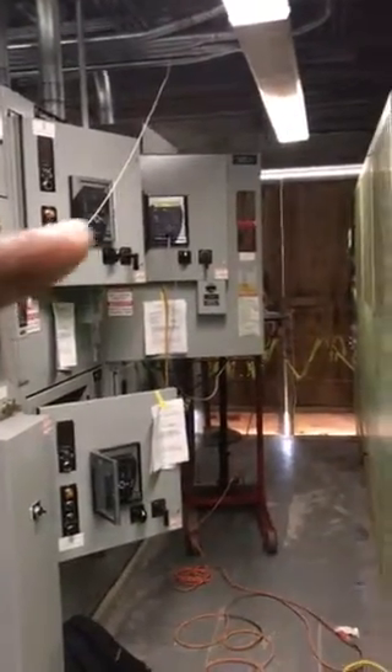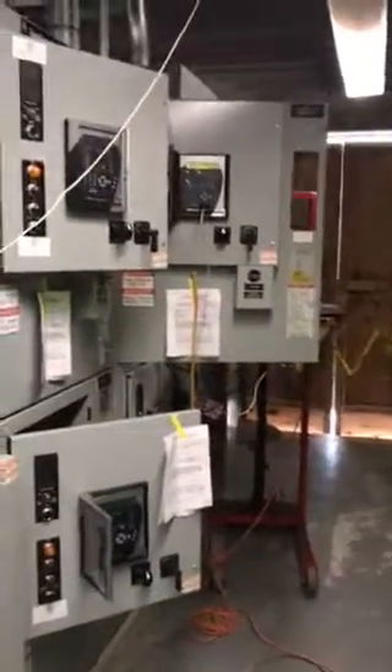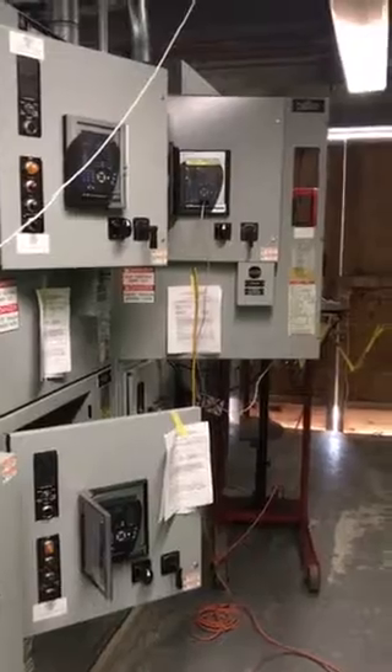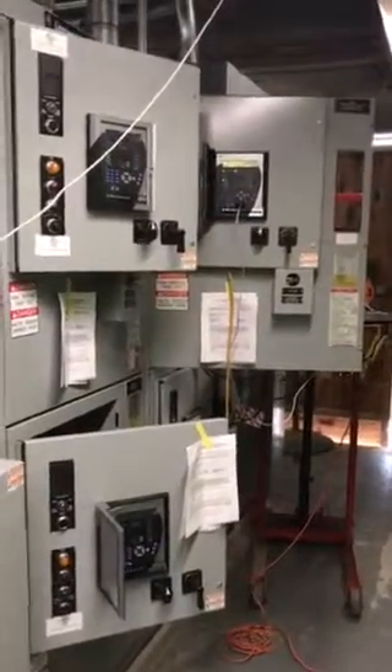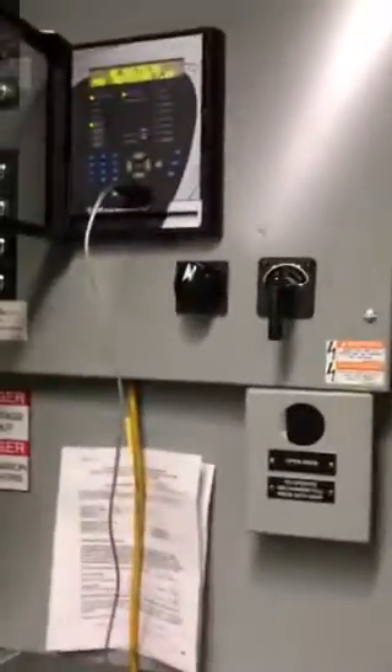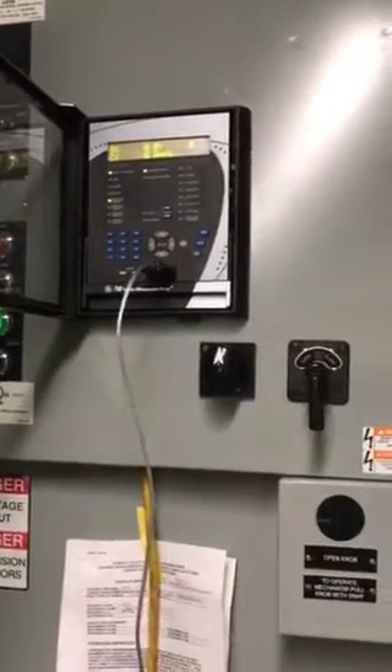Those four doors that you see down there — you can kind of see the fourth one — these are cubicles that control motors, transformers, or any other type of major industrial load that your customer would like. My customer would like me to inject actual current on the primary, and I'm interfaced with my relay right here: a GE750 relay with my EnerVista software up.